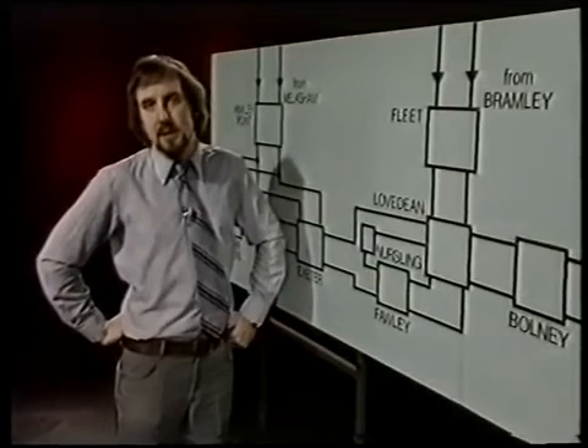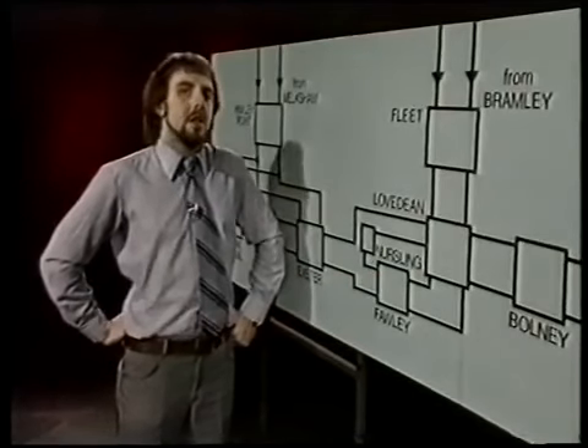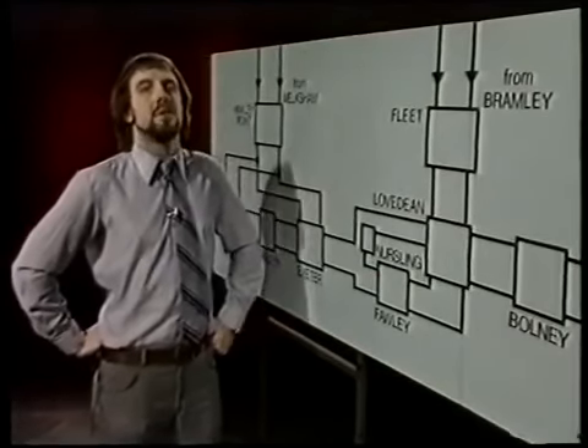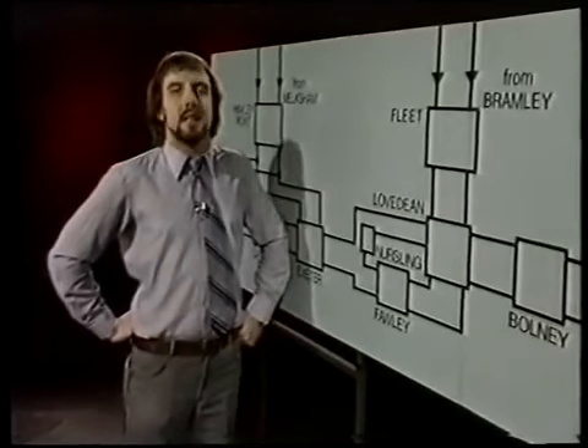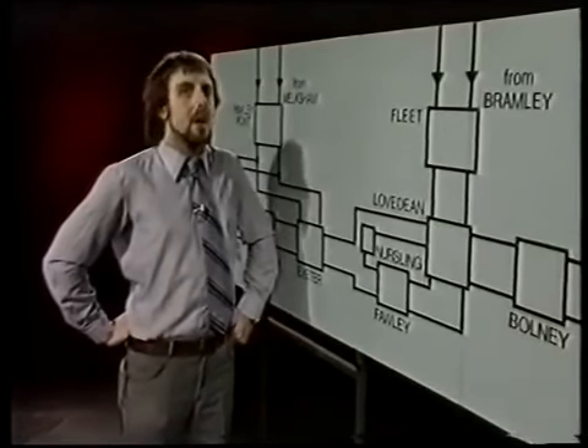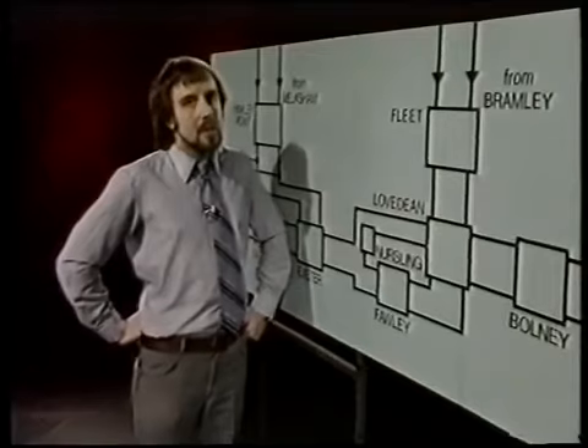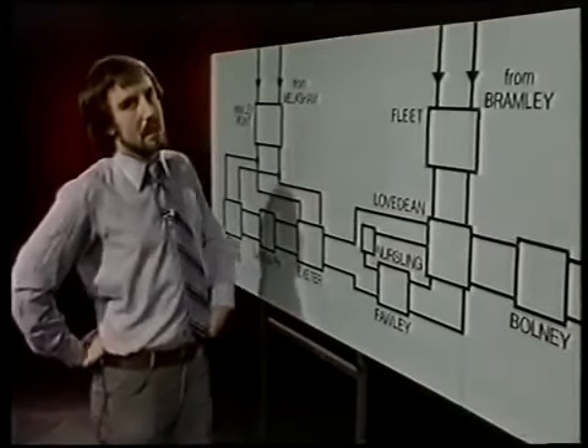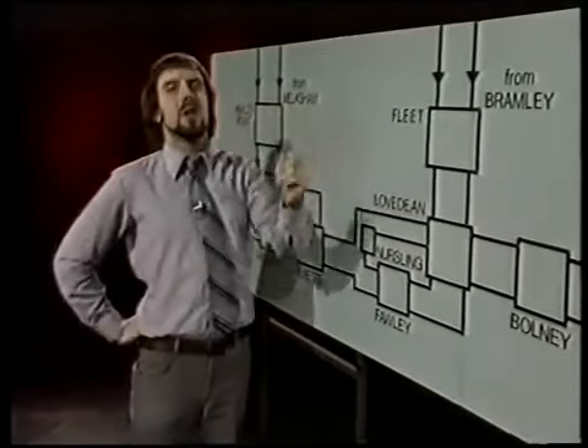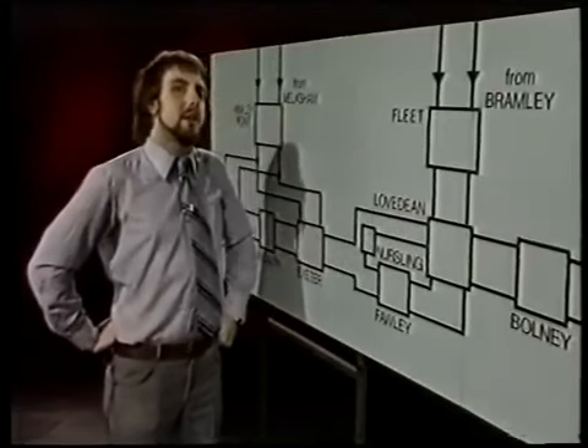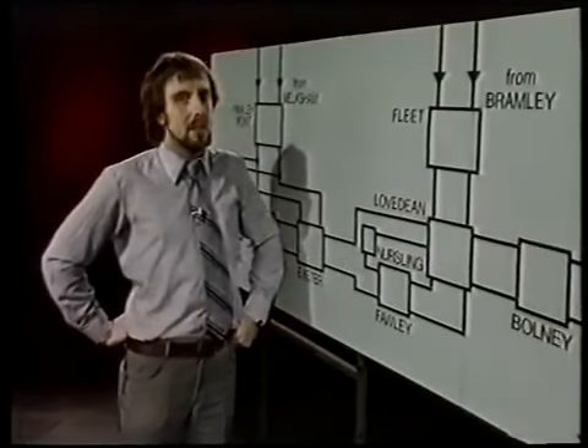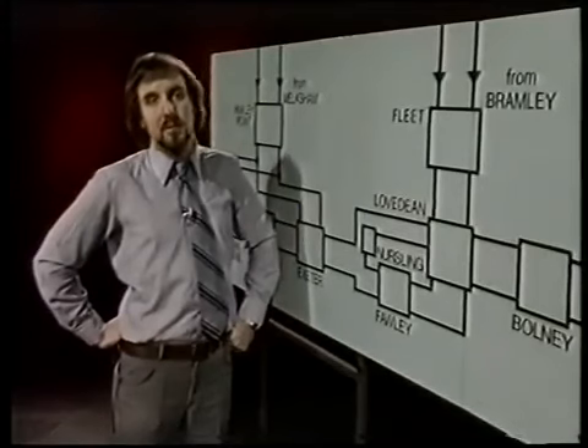But what happens during the evening peak? Let's assume the online models predict that the Bramley-Fleet line is getting near saturation. If a line goes down, this would tend to overload both of the other north-south lines here and here, causing them to trip out—that is, they would be taken out of service automatically to protect them from damage.